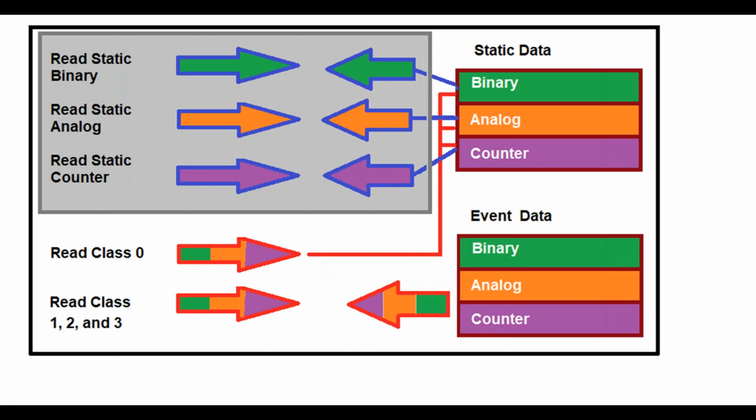Most of the presentation on objects so far has talked about individual input and output objects. While outstations use the input objects to report point data to the master, most master read requests do not explicitly ask for these objects. They can, but they typically do not. They ask for what is called class data and issue what are called class data polls.